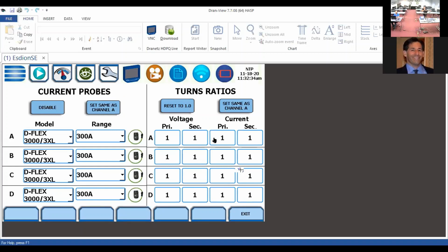The turns ratio comes into play for medium and high voltage applications where the instrument is basically piggybacked on existing PTs and CTs. A very common medium voltage application is 4160, or 4.1 kV. Obviously, you can't bring those voltages directly to the instrument as it's rated up to 1,000 volts. So typically in those applications, the instrument is connected to existing PTs for the voltage and CTs for the current. That's what we mean by piggybacking off existing PT and CT secondaries. Rule of thumb: if you're direct connect, up to 1,000 volts, then these values basically remain at 1. But in cases where you're going to piggyback off existing PTs and CTs, you need to know what the ratio of those devices is.